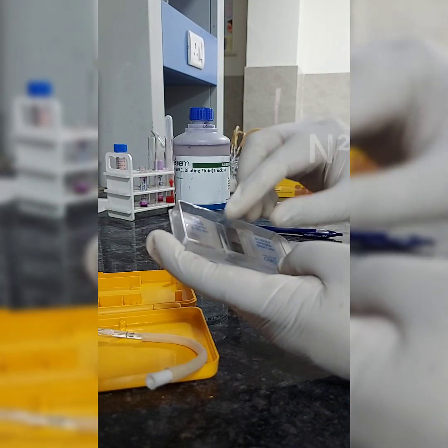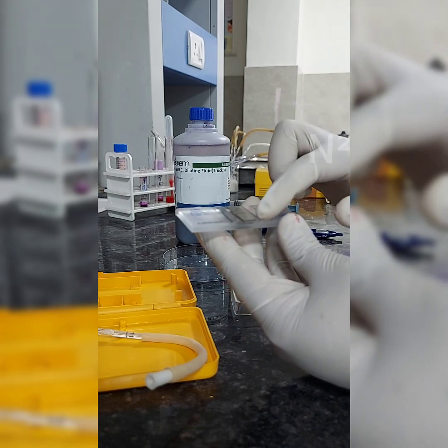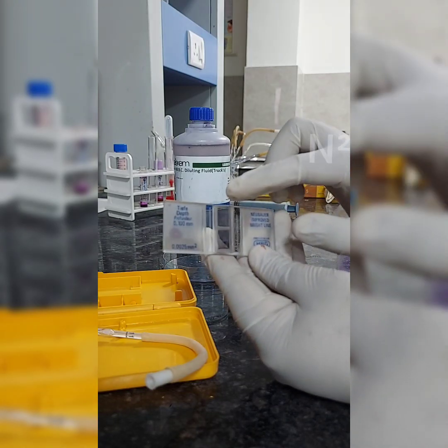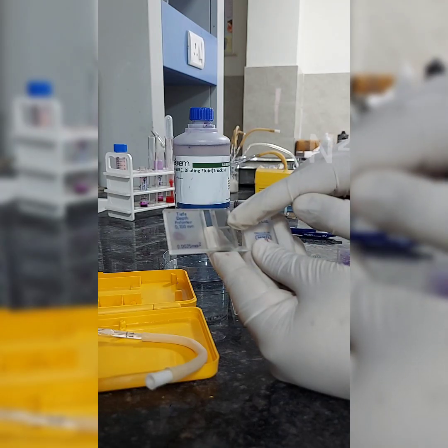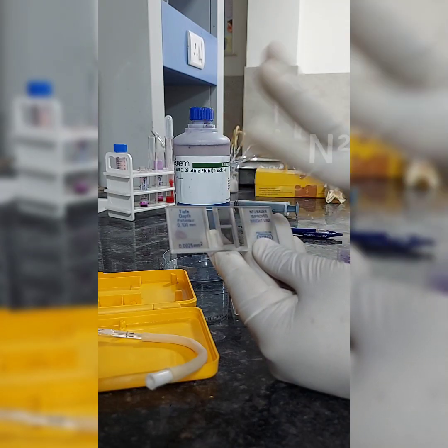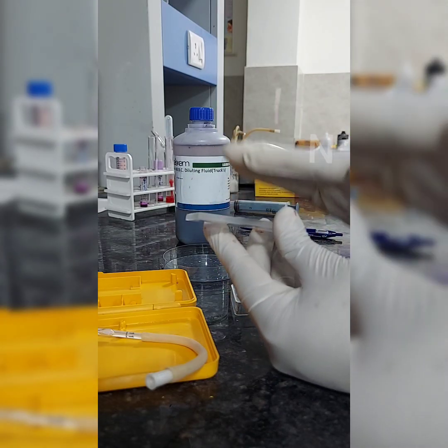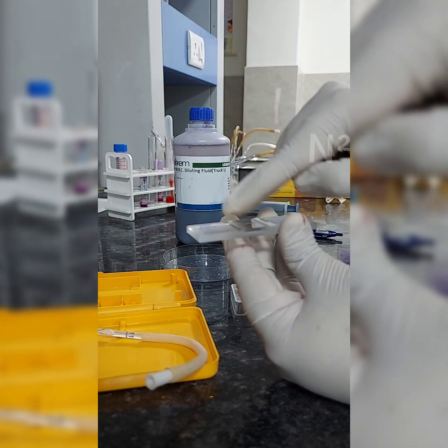This is the hemocytometer slide with improved Neubauer counting area. We have discussed this hemocytometer slide. We have the lateral platforms, the elevated raised areas on either side of the central shiny area, which is called the Neubauer counting area. We have an H-shaped groove or gutter. On either side the raised platforms are at a height of about 1/10 millimeter. So if we place a cover slip on top of this instrument, we get a gap of 1/10 millimeter between the cover slip and the Neubauer counting area, which is used as the Neubauer chamber for our counting.